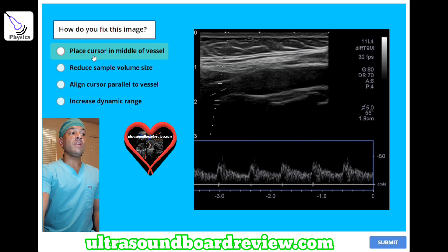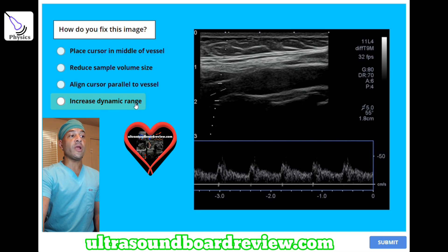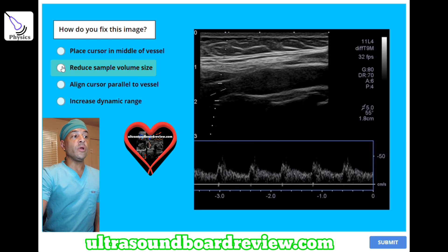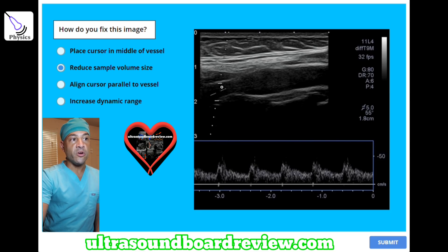How do you fix this image? A) place cursor in the middle of the vessel, B) reduce sample volume size, C) align cursor parallel to the vessel, or D) increase dynamic range? The answer is B, reduce sample volume size to reduce or eliminate the spectral broadening. You can see that the sample gate is too wide, so narrow it down to help eliminate spectral broadening.